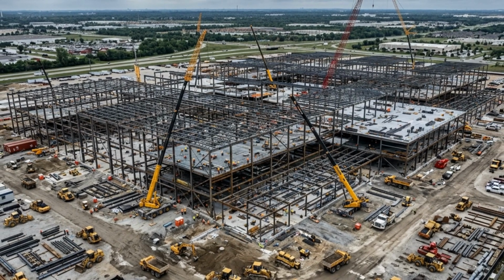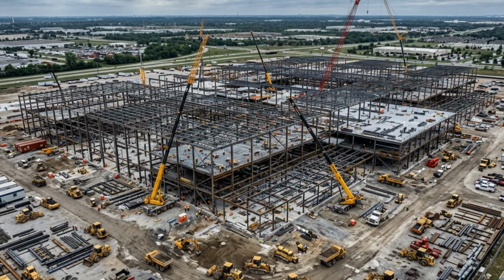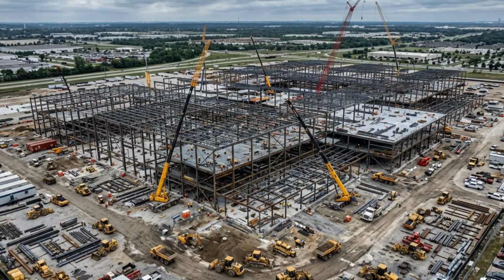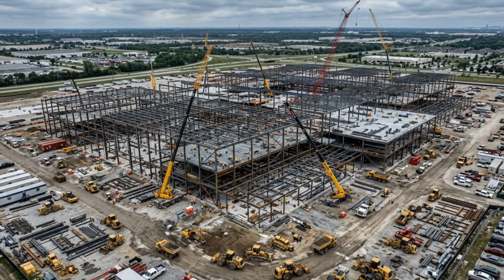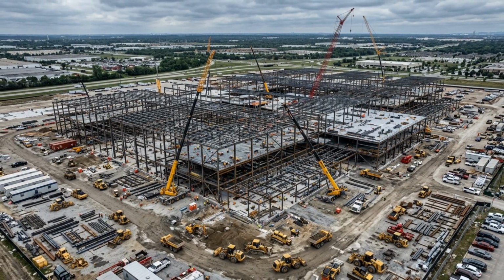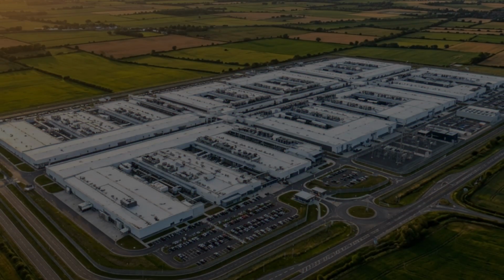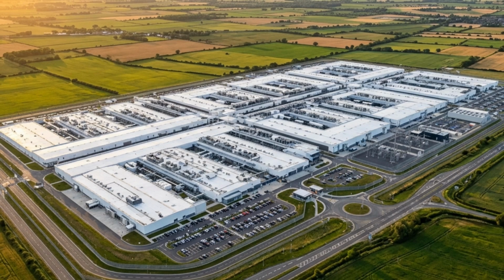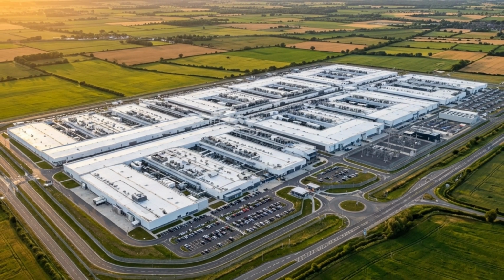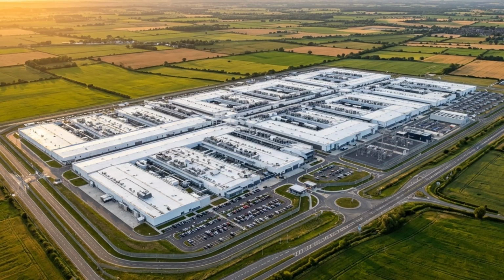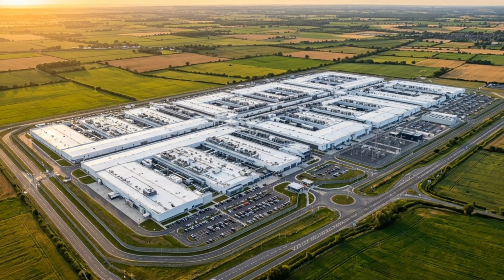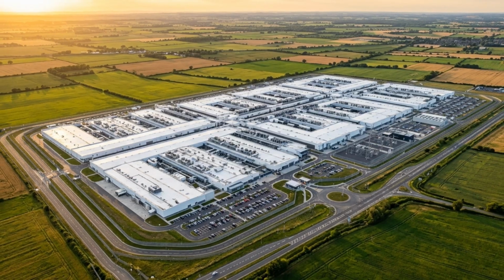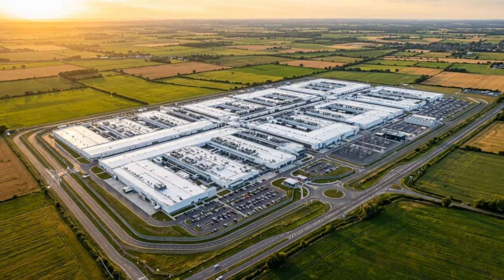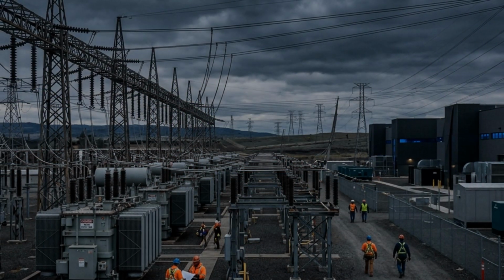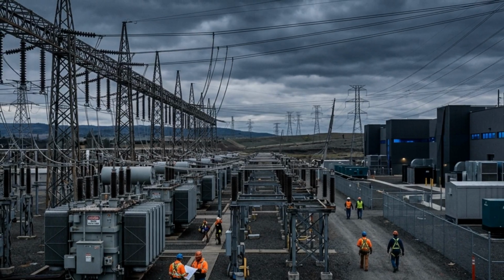All of this computing generates enormous quantities of heat, and heat is the enemy of electronics. Left unchecked, it will throttle performance, degrade components, and eventually destroy hardware entirely. In a traditional data center, cooling is handled by computer room air conditioning units that blow cold air through raised floors and up through the server racks. This works reasonably well when power densities are modest, but in an AI data center, with racks consuming 100 kilowatts or more, air simply cannot move fast enough to remove the heat. The physics do not work. Air has a limited capacity to absorb thermal energy, and at these densities it reaches its limit before it reaches the back of the rack.